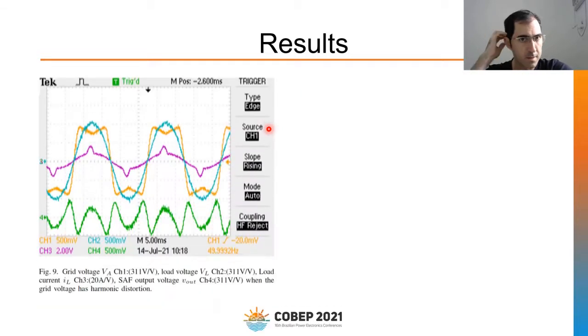Let's check some results. The first one is a classical steady state test. We have here in orange the distribution system voltage. We can see that it is distorted. If we did not have the series active filter, any load would receive such a distorted orange waveform. But with the series active filter working with the designed controller, we can see that the load voltage is a sinusoidal waveform. Here in purple is the load current, which in this case is a combination of a linear and nonlinear load. And in green is the output voltage of the series active filter. The orange plus the green results in the blue waveform.